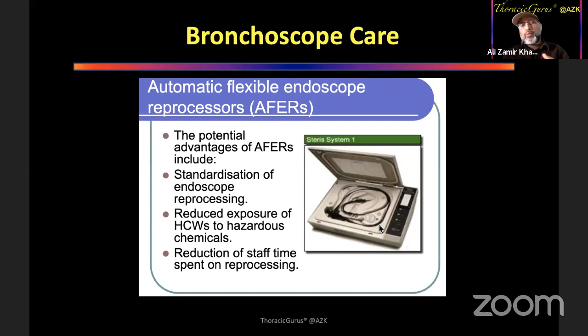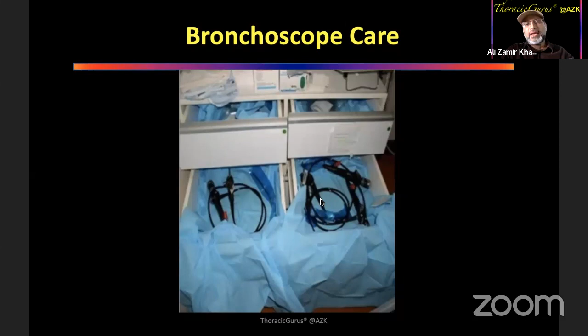Storage of the bronchoscope is very, very important. When you've done all of this cleaning, you've got to make sure that each bronchoscope has its own area to be stored, and vertical storage is better than horizontal storage. So personally, in our theaters, we have vertical storage. You hang the bronchoscope from a hook on the top. There are slots for 10 or 20 bronchoscopes, and you hang each one of them so that the fiber optic cable doesn't get bent and doesn't get snapped. So vertical storage is better than horizontal storage. Personally, I like my bronchoscopes to be stored vertically rather than horizontally.